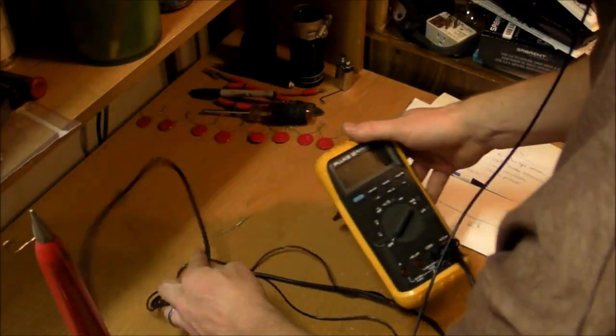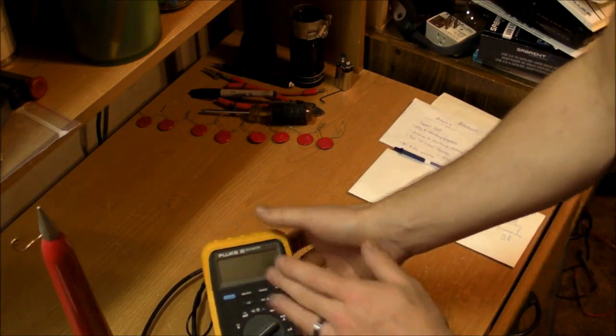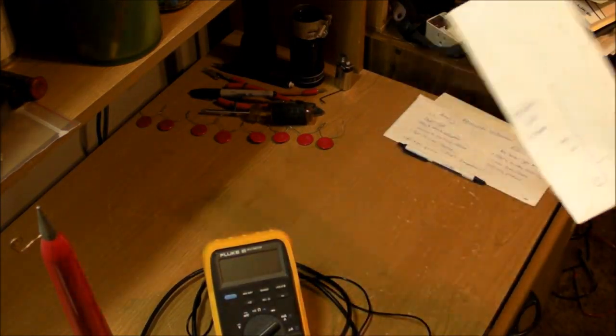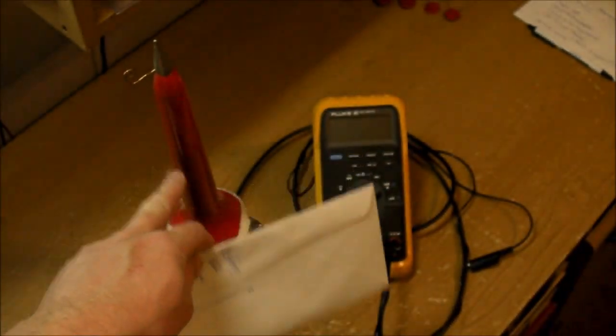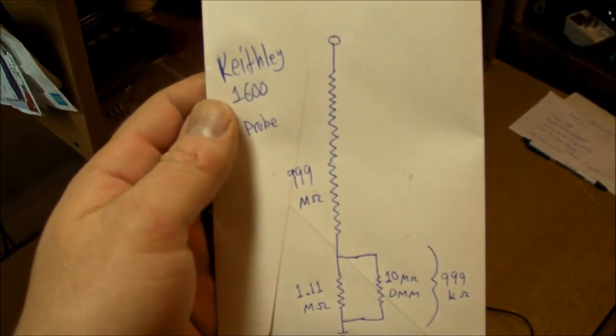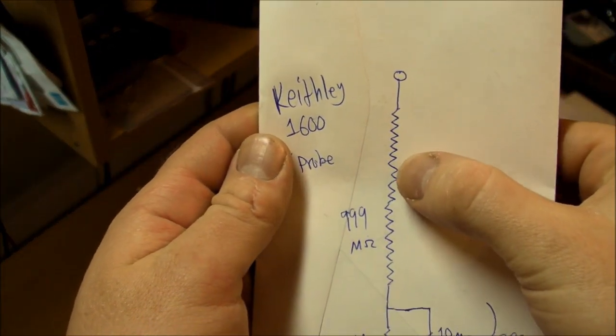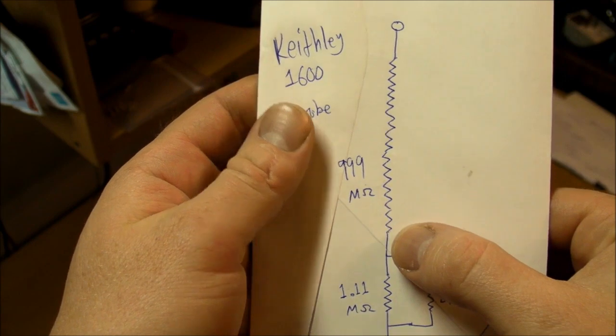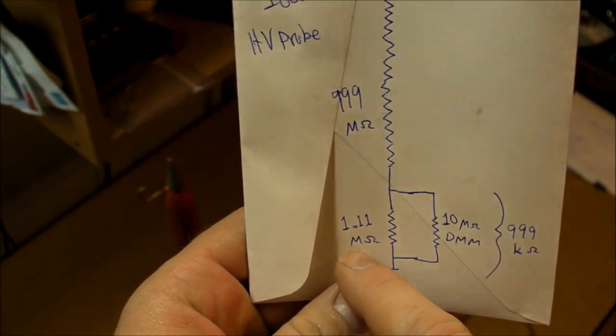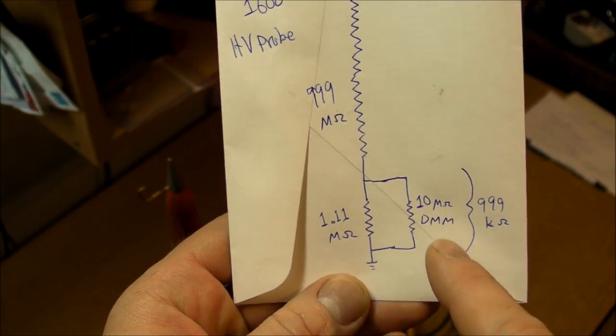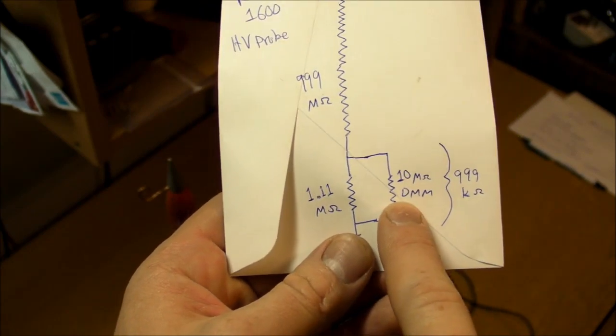It goes straight into a DMM like this with a 10 megohm impedance. The main body of this probe inside the red stick is a very long 999 megohm resistor.